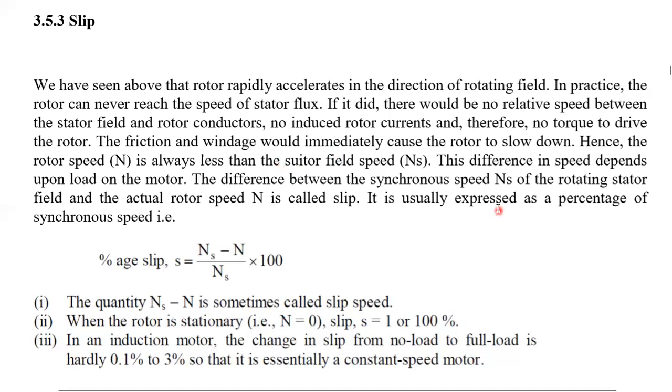Then there is a speed difference between the stator rotating magnetic field and the rotor. That is called slip. The difference in speed depends upon the load on the motor. If the load is increasing, speed decreases. If the load is decreasing, speed increases, but it never reaches synchronous speed.